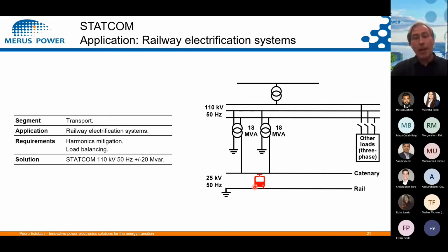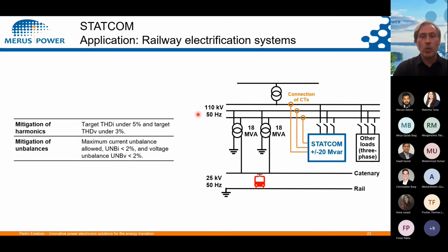When the train is passing through the substation, or where we are located, there will be an imbalance created because of this connection. This imbalance will be affecting other loads that we might have there, that are 3-phase loads, and it could also be affecting any other users that we have in the same system. So a solution for this could also be a STATCOM.